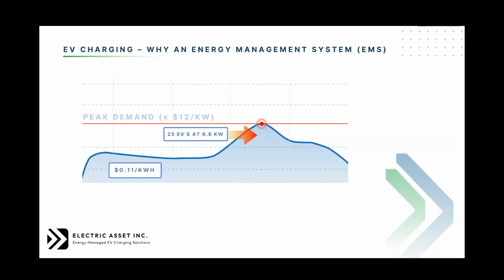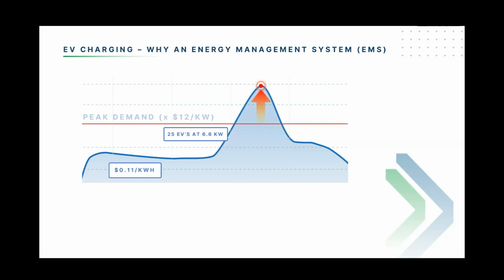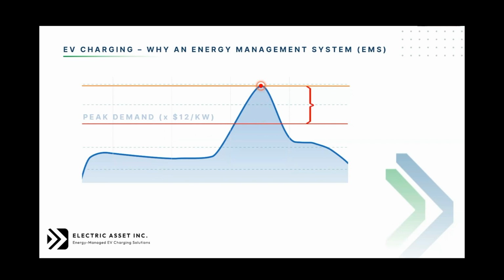So each EV will use 6.6 kilowatts of energy. Without anybody knowing, the blue line doesn't change that much because it's only 11 cents a kilowatt hour. But this one incident, for just one day during the month, has driven up the peak demand on this building's pricing system. This one event, with 25 electric vehicles using 6.6 kilowatts, is 165 extra kilowatts of demand. At $12, that's $2,000. So this one event cost this building $2,000 above.